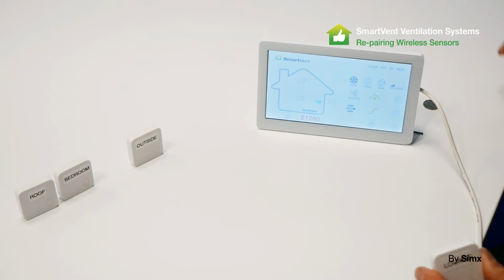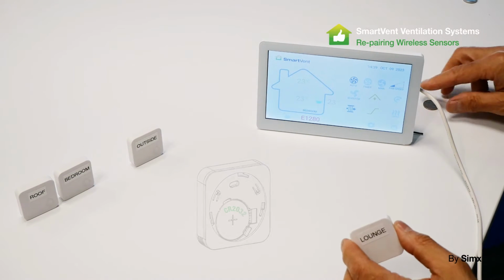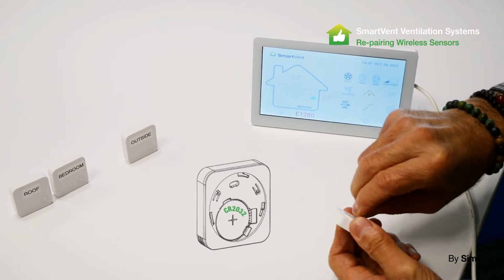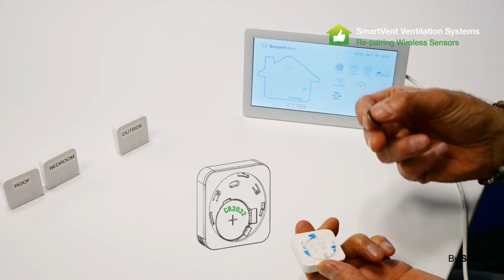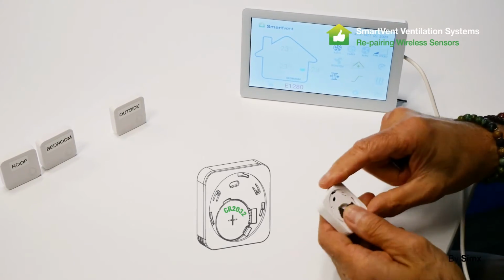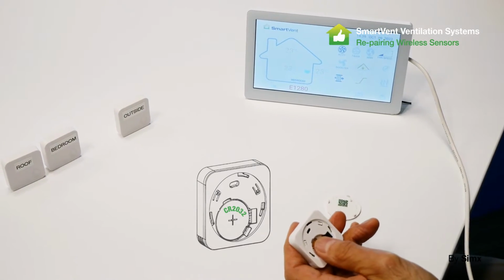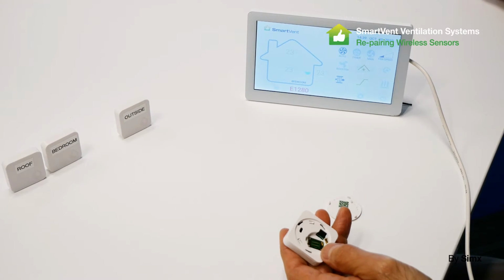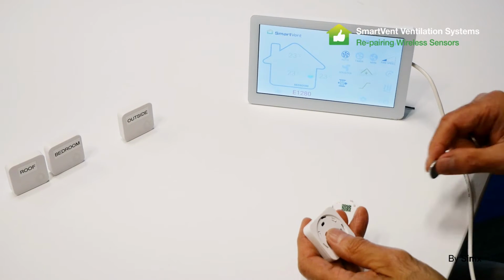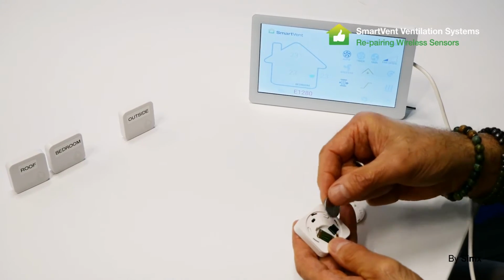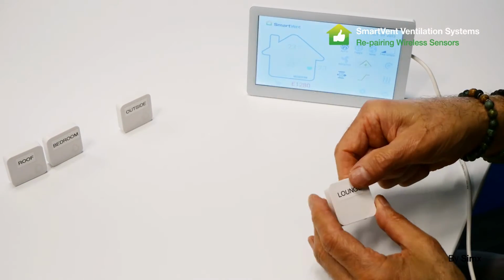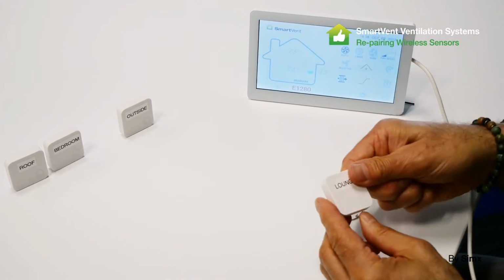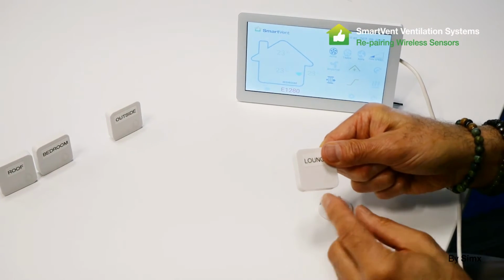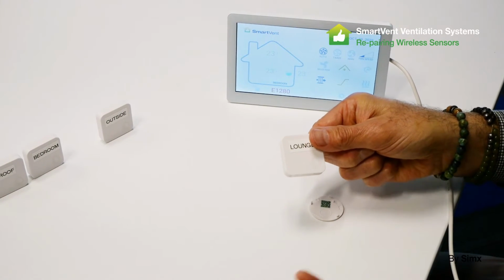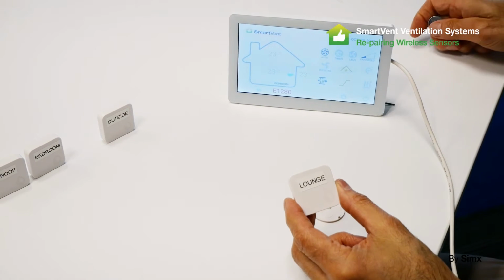So what we're going to do is replace the battery. If I take a coin to remove the battery cover - I've taken the battery out just to simulate the fault - but you would remove the battery, replace it with a new one, put the cover back on, and try pressing the button again. You should see the red LED come on. If it doesn't come on, then the sensor's failed.